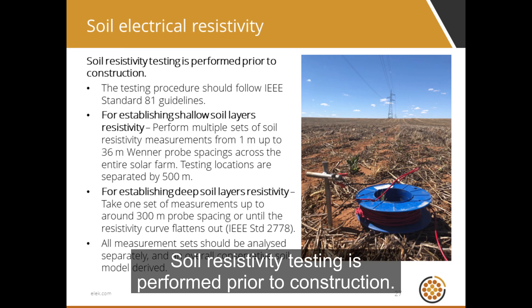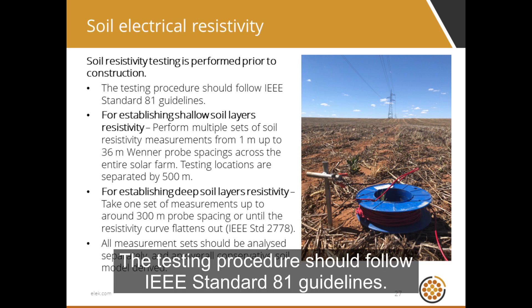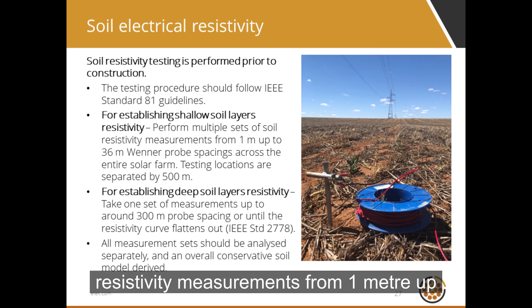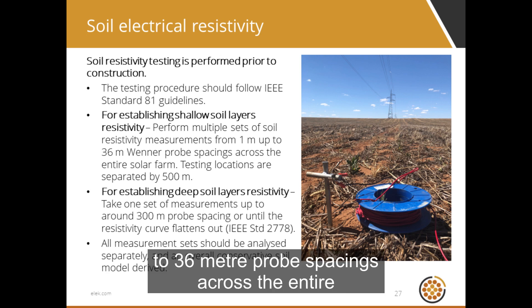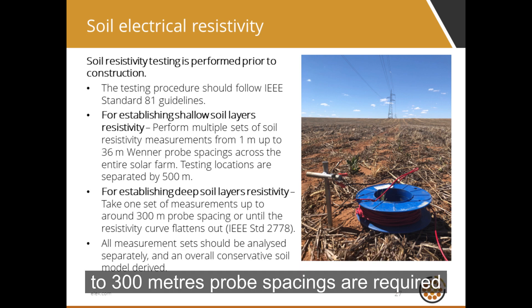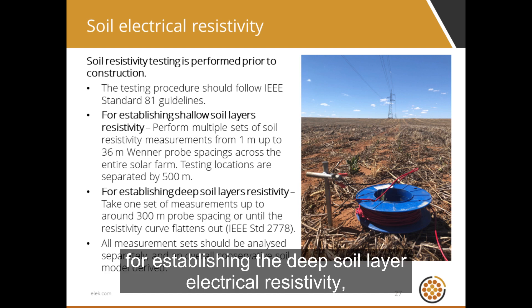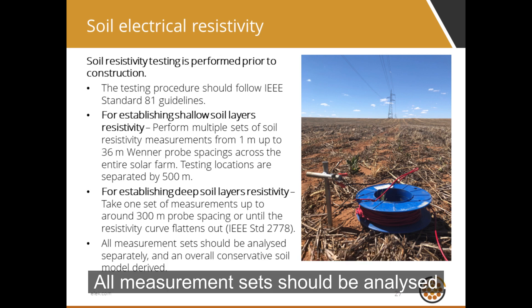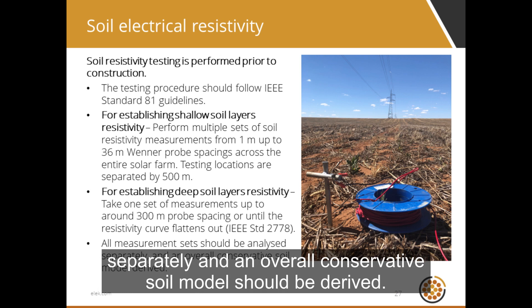Soil resistivity testing is performed prior to construction, following IEEE Standard 81 guidelines — note that a new version of this standard is being released. We recommend performing multiple sets of soil resistivity measurements from 1 meter up to 36 meter probe spacings across the entire solar farm, with testing locations separated by 500 meters. A single set of measurements of up to 300 meters probe spacings is required for establishing the deep soil layer electrical resistivity, useful for fault current distribution calculations. All measurement sets should be analyzed separately, and an overall conservative soil model should be derived.